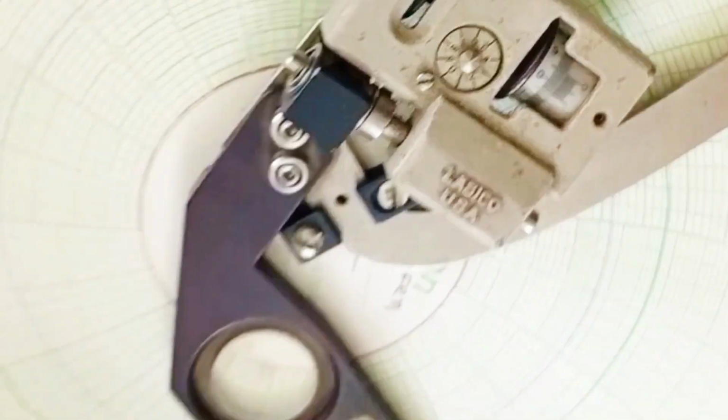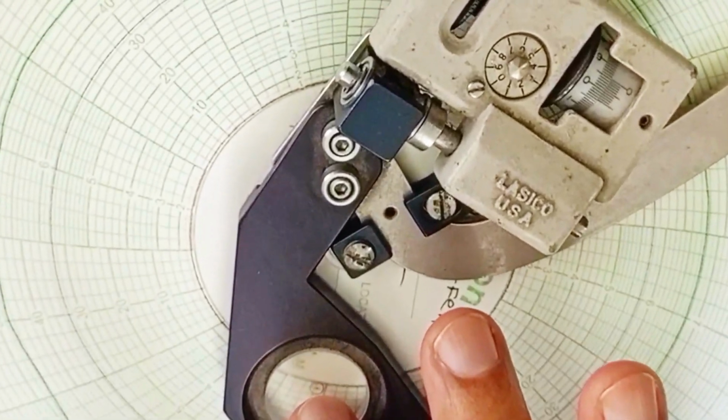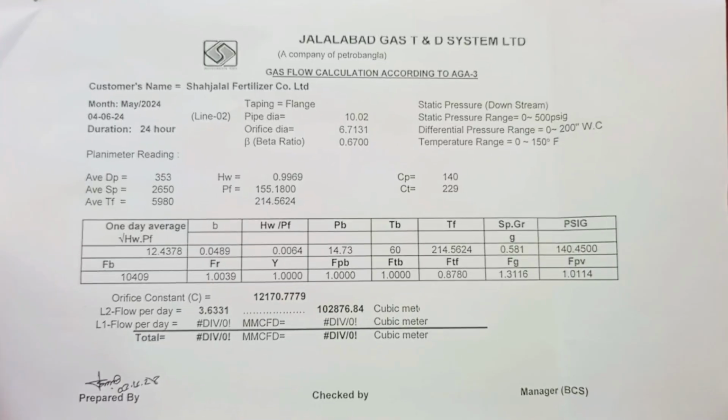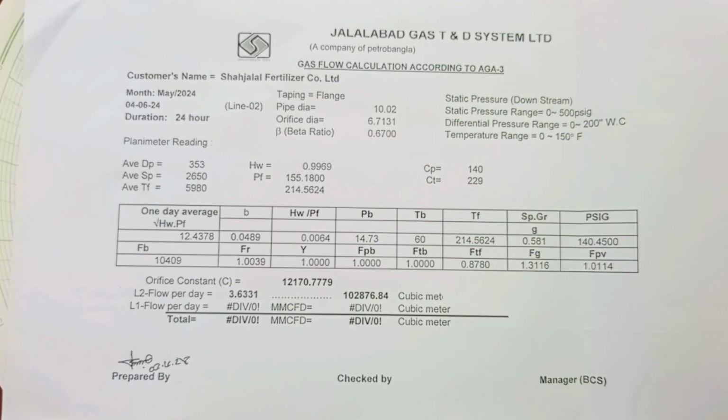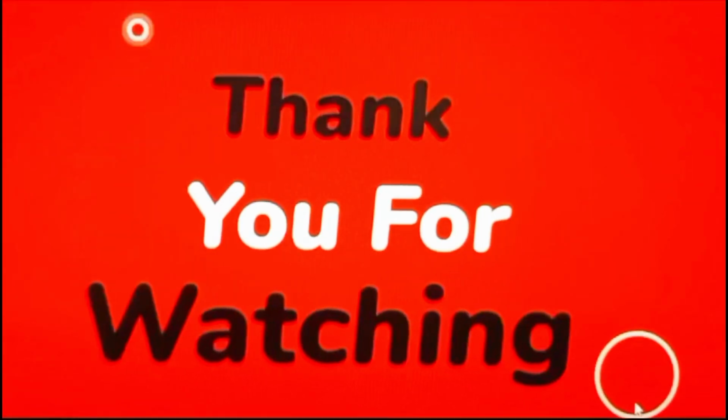Heating value depends on the country and the pipelines, so the value can differ from 34 to 52 megajoules per cubic meter, and likely 950 to 1050 BTU per SCF.